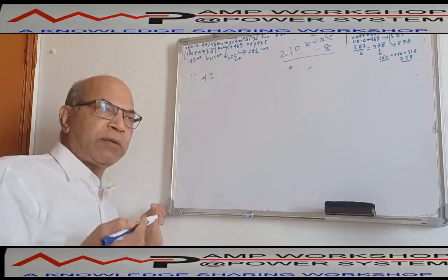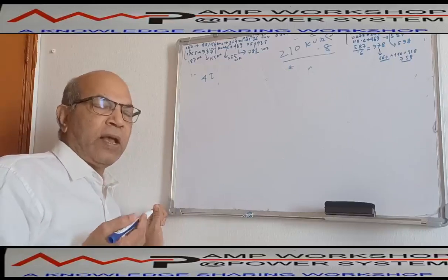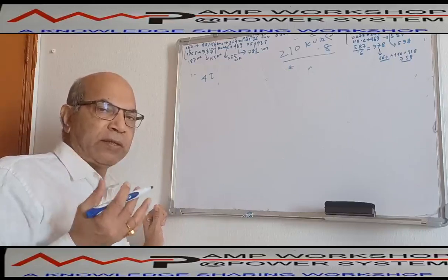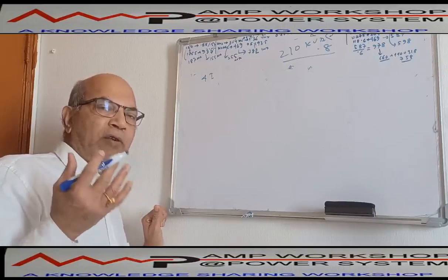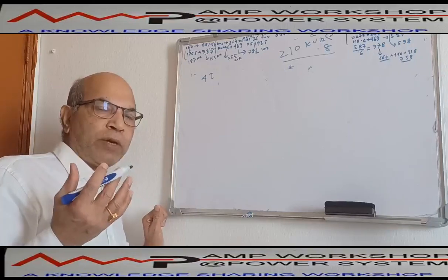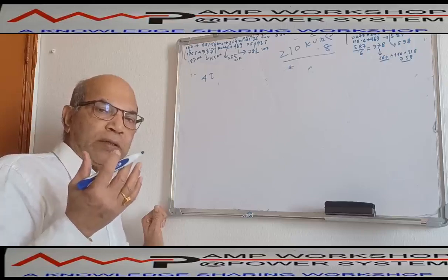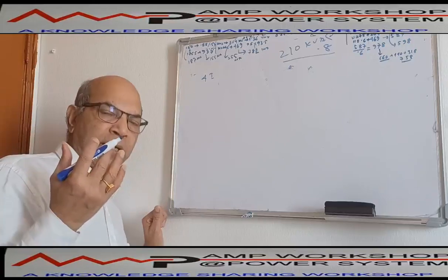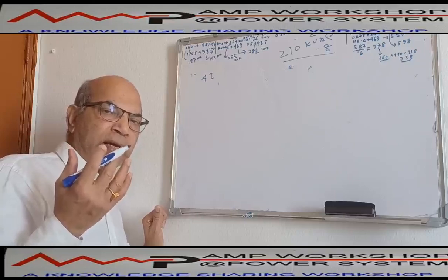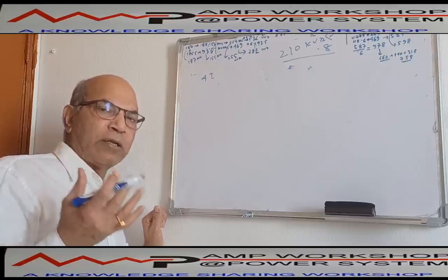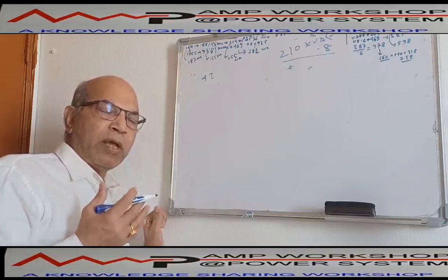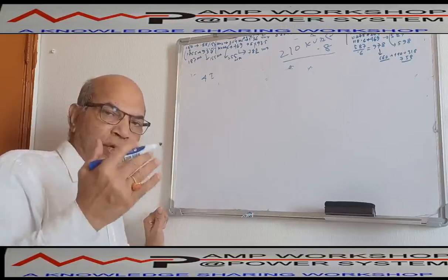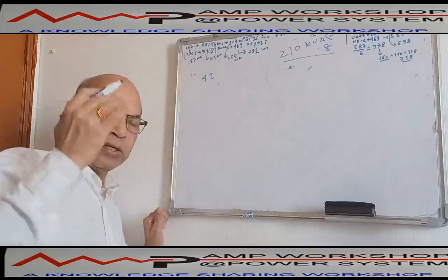So the initial phase of the current is fully reactive in nature, and the active current is very less. As the reactive current is very high, the power factor of the motor is very poor, because we know the power factor of the motor depends on kilowatt by kVA. Now if the kilowatt is less and kVAR is more, then it will be more reactive in nature.